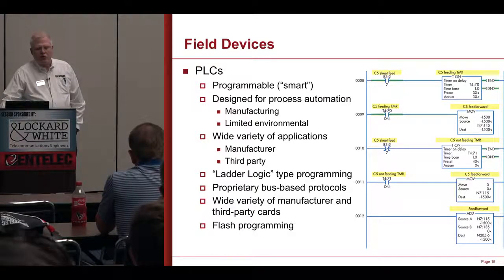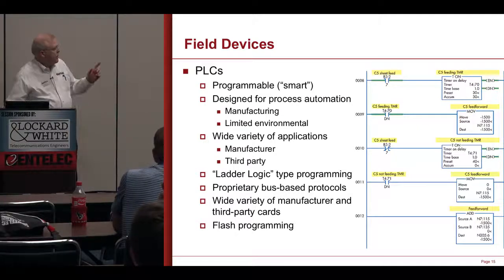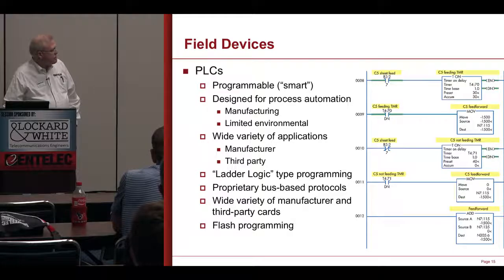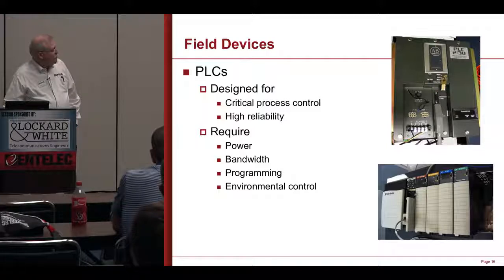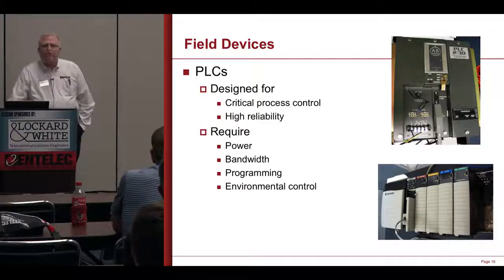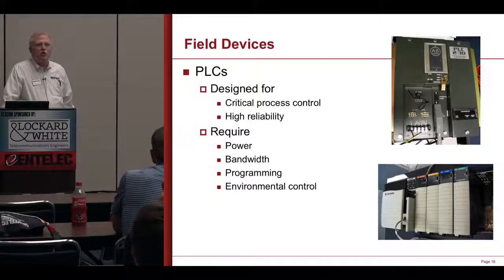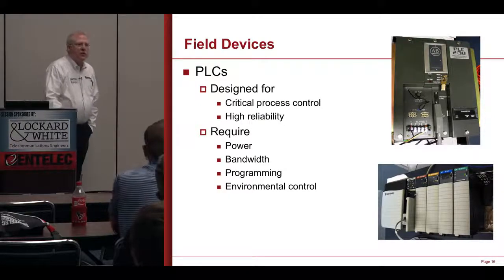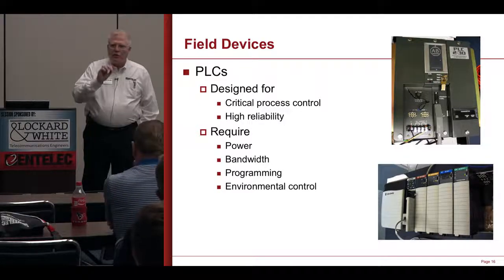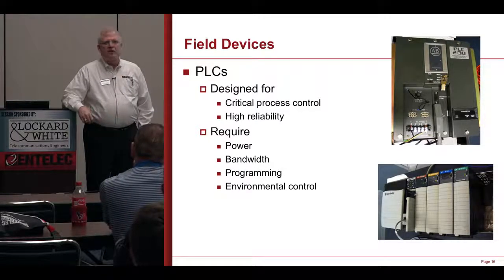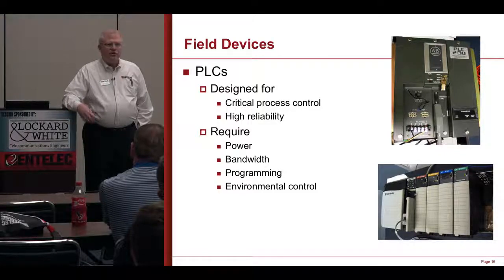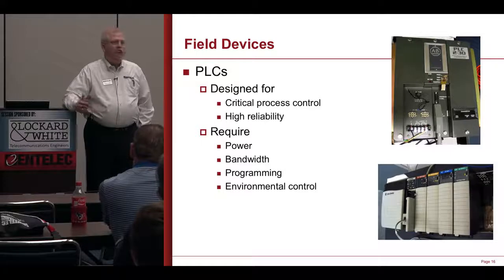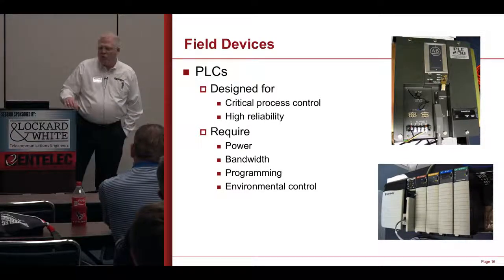PLCs also support other kinds of programming and have a lot of proprietary buses. They're designed for process control and high reliability — I'm not going to lose control of the process. They require power. Where an RTU is almost always low power and designed to run off solar kits, PLCs, particularly the bigger ones, are not really designed to run off batteries. If you put them on batteries, the solar array and battery kit can be tens of thousands of dollars.